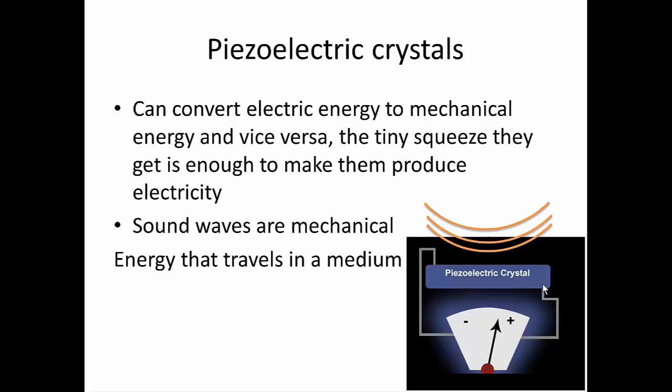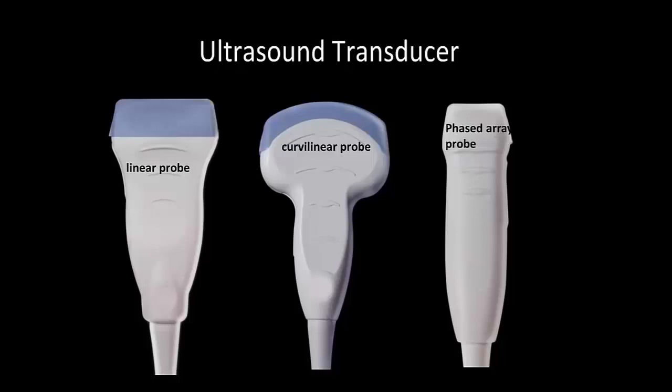The indirect piezoelectric effect is when we apply electricity to the crystal, which will then make it shrink and expand — and every time we do that, we emit a sound wave. The direct piezoelectric effect is receiving sound waves and converting these into electricity. Whenever that happens, we can use a computer to integrate this information and generate an image out of the received signal.